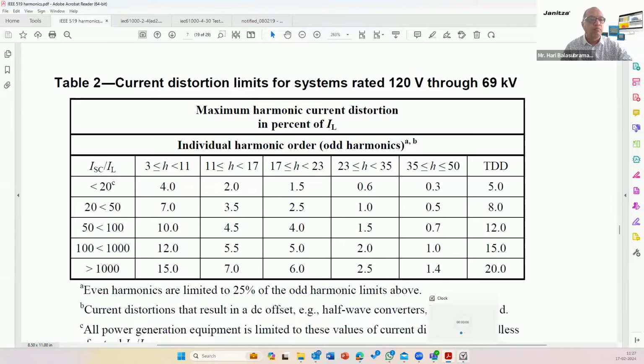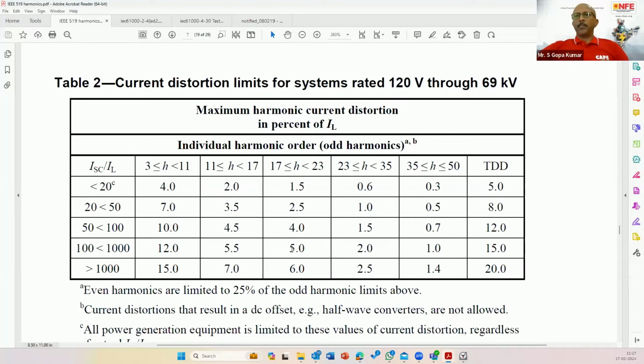The grid doesn't exhibit a constant short circuit level. It can offer a very high short circuit level at industrial areas, IT sector areas, and city centers, but in rural areas with the same developing industrial premises, it will be weak. Some grids exhibit 10,000 MVA fault level at city centers and 1,000 MVA at rural centers. The consumer has no choice in this. So implementers arrive at a common methodology to avoid grid-to-grid differences in ISC and the cumbersome process of calculating TDD — they simply declare an average value. For example, instead of 10,000 and 1,000, if they declare 6,000, most consumers will be escaping compliance.